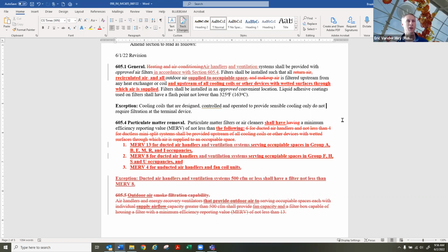Well, there are different types of heat exchanger. A wheel is going to have some leakage, right? And it's allowed to have up to 10% leakage per code. Most wheels have under 1% leakage. But it's still required to have a filter upstream of it to protect the total enthalpy wheel. If you have a sensible and latent core, it's going to have some leakage between the two airstreams, and that leakage again is allowed to be up to 10% per code. So typically the air coming back has to be filtered to protect the energy recovery heat exchanger. But do we only need a MERV 6 filter there, or what do we want?